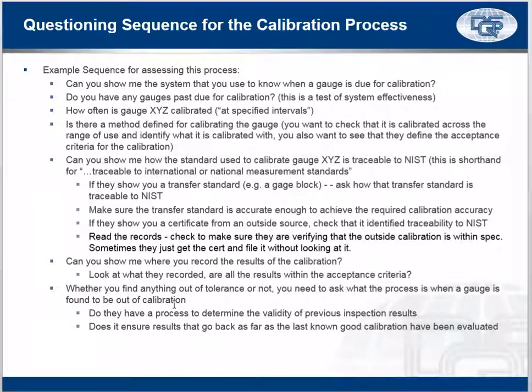I've been surprised at how few of the systems I've audited in the last year have actually had this requirement being met. And I've been surprised because this has been a requirement in the 1987 version of the ISO standard. Even if you do not see a sample where a gauge was found out of tolerance, you need to still test that system. You need to see that it's documented. You need to ask them what they would do. You can ask them if they've had any that have been out of tolerance. But you need to make sure they have that process.